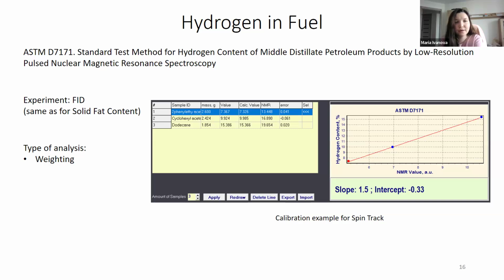The experiment is also very simple. It's FID, the same as for solid fat content. But here, there is only one type of analysis. It's weighting. Before the measurement, we weigh the sample and condition it at the required temperature. Then we acquire the FID, record the averaged amplitude, and make some calculations, getting a linear curve between the hydrogen content and the NMR value, as you see on the slide.